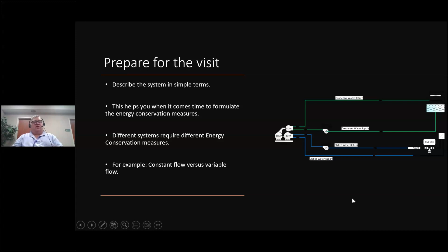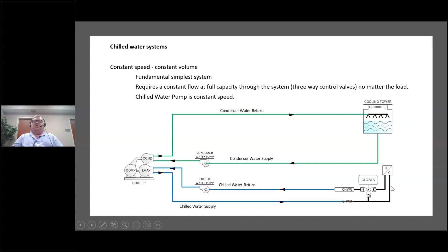For example, a constant flow system versus a variable flow system - you will not use the same ECMs on those two systems, even though they're fundamentally basic. But you have to know the difference between one and the other. This is an example of a constant speed system. There's only one path to go, and this is about as simple as I can make it: constant flow all the time on both circuits, no change, no variable speed, no variable flow. But could I put this into one sentence? Sure - it's got a control valve to control the flow at the coils, and that's about it. All the pumps are constant speed, the chiller takes all the water no matter what, and there's no change in the operation.